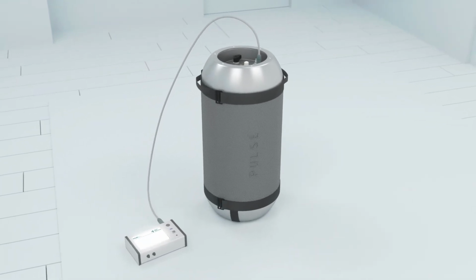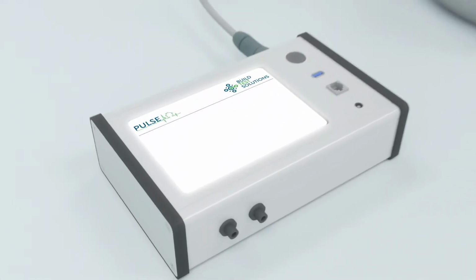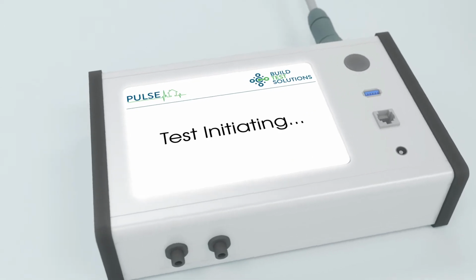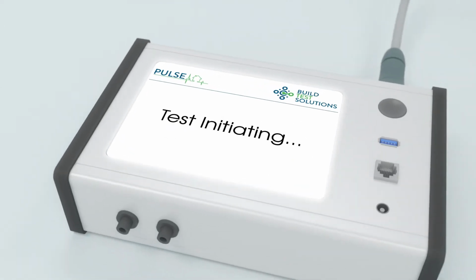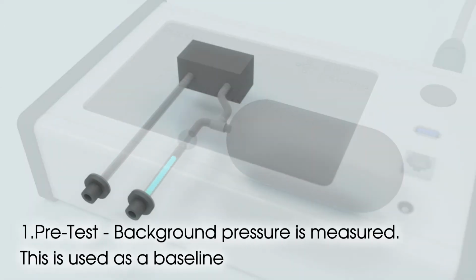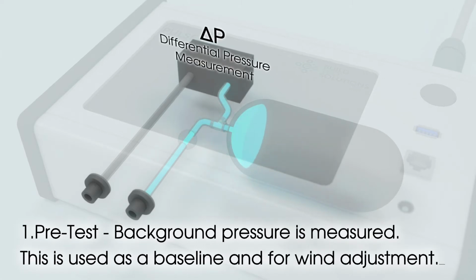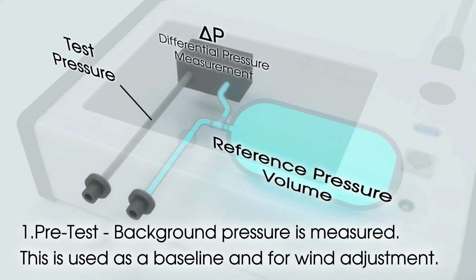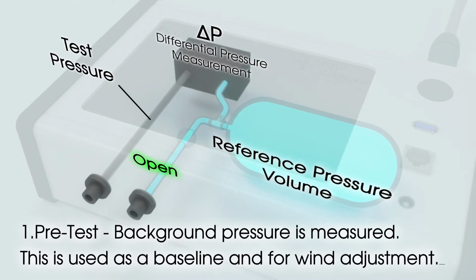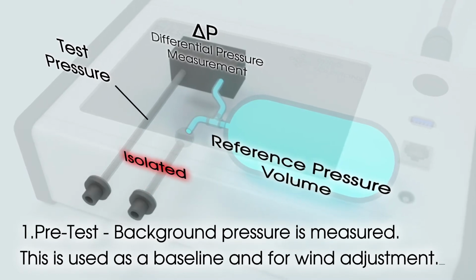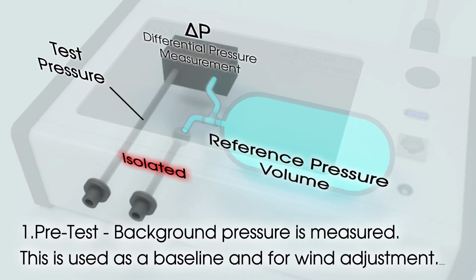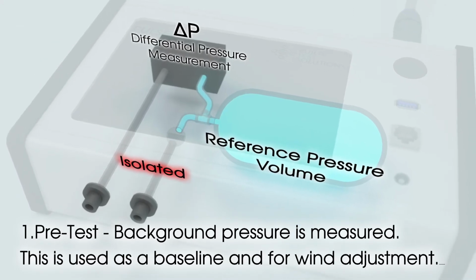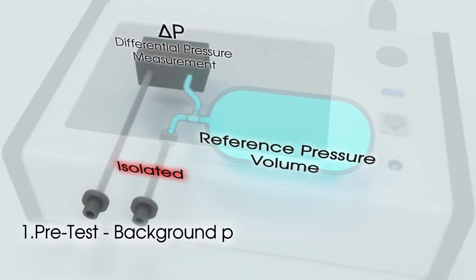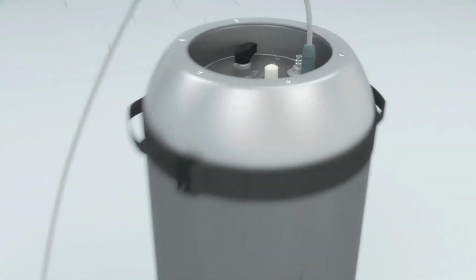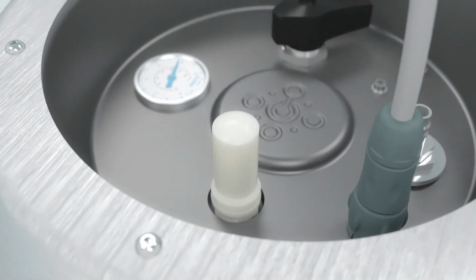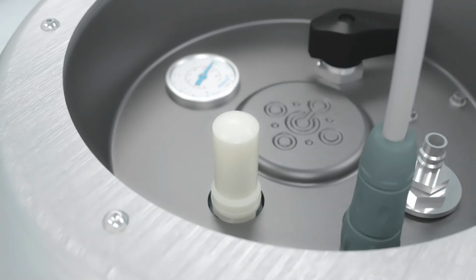The air receiver is positioned centrally in a ground floor room and charged to between 3 to 10 bar while the building is prepared for the test. The air release measurement itself takes less than 10 seconds. First, a small airtight vessel is sealed to provide a reference pressure, and a 2-second measurement of the background building pressure is recorded. This approach means that no penetrations to the outside of the building envelope are required as part of the test. And with that, the whole building fabric airtightness is measured.